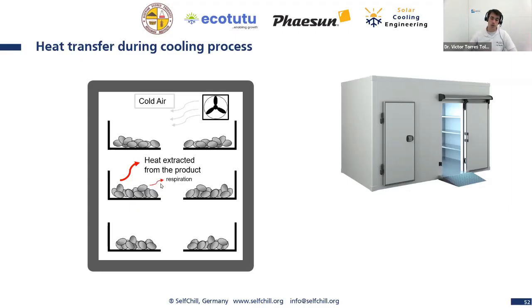What else? We have also respiration inside the cold room. This is the energy delivered by the products because they are living plants, right? So they consume oxygen, emit CO2, and they also deliver energy. So we need to double check for every product if the amount of energy they deliver by respiration is considerable or not. I told you already, this is not considerable for every product, only for a couple of them, but we always need to double check. What else? The thermal losses, right? So imagine we have outside 35 degrees, and inside we have 10 degrees, and we have an insulation thickness of 100 millimeters. So we can calculate how much thermal loss we have, how much cooling energy gets lost, or how much heat energy we get inside, right?